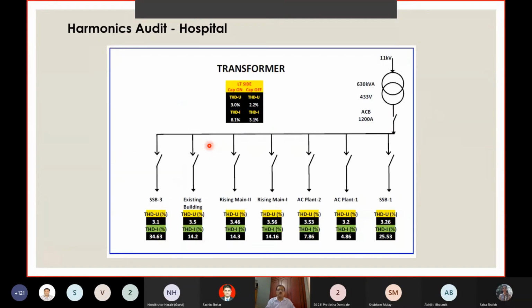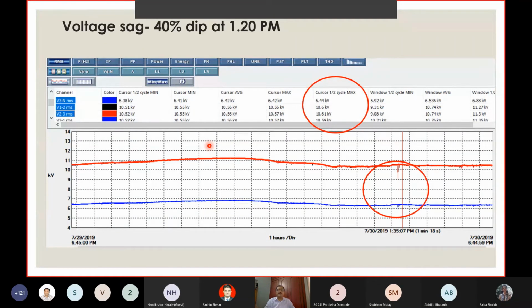So I'll try and show a case study here. Same hospital, 6:45 p.m. to 6:45 p.m. on 29/7 to 30/7, 24-hour reading. They have encountered a dip in voltage in one of the 3 phases, as you can notice here. Cursor half cycle is 10 millisecond, right? So the cursor half cycle has captured this. And there was a sudden dip at around 1:20 p.m.